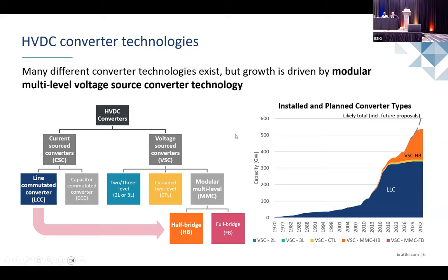In current source converters, these converters are based on thyristors. In voltage source converters, these are IGBT based. Both current source and voltage source do conversion, but they have different characteristics, and because of those characteristics, you get different functionality out of these converters. As I said, current source converters we can again classify into line commutated converters and capacitor commutated converters. The capacitor commutated converter is very similar to the line commutated one, but the difference is that it is similar to series compensating capacitors.